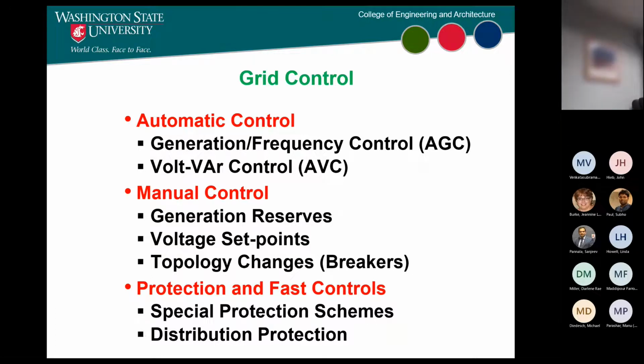Who sets these? Let's say you've got a voltage controller that wants the voltage to be at 1.03. Somebody sets that. Why not 1.01? The reason is somebody determined it beforehand through voltage studies, saying it has to be 1.03 here because by the time you control the voltage at the end of the line, it's probably a lot less, and so on.